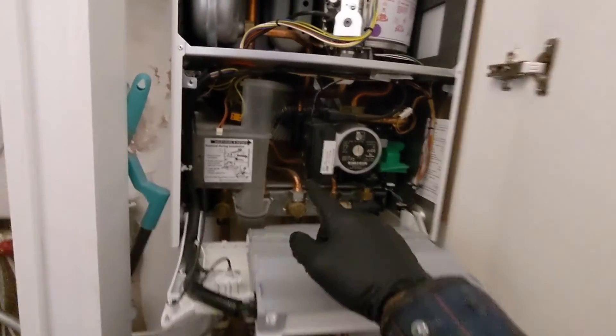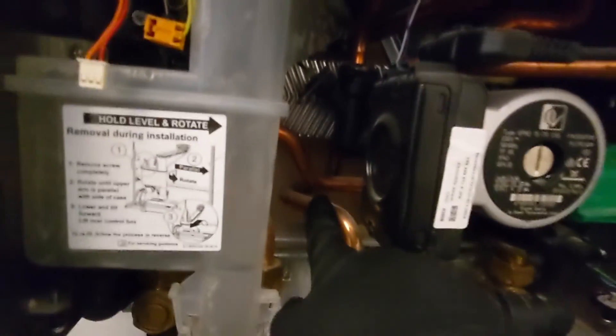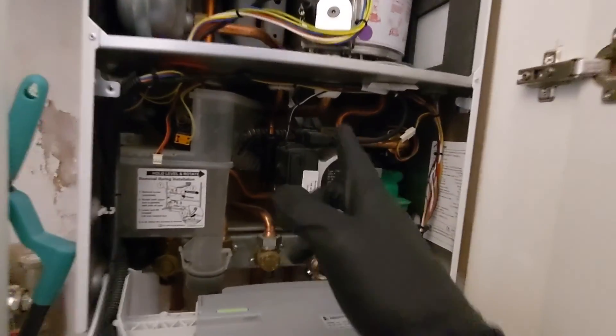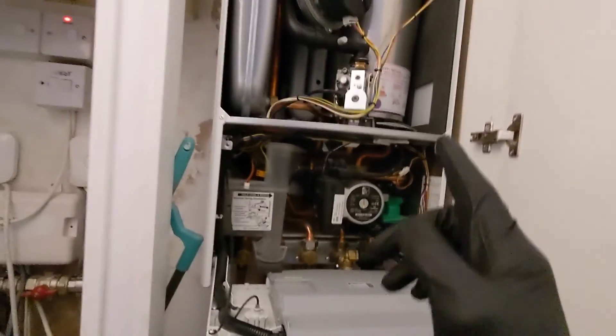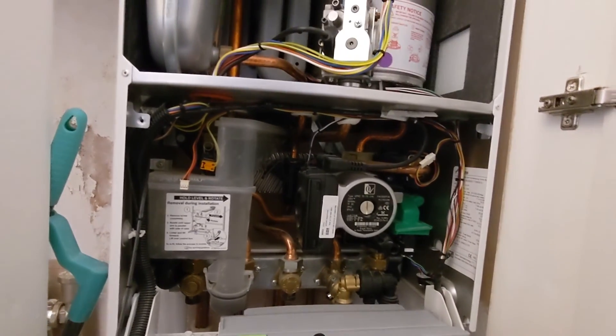These ones are not like the older styles where I could drop the plate out the back, because you've got the gas pipe here in the way. I've tried it before but that gets in the way, so it looks like I'll probably have to take the pump and everything out and then take the plate out the old way. I'll see if there's a way I can drop it out the back by looking underneath, but from my first attempt on the ERP ones I couldn't do it. I think I have seen a couple of people do it before, so I'll give it a try — if not, we'll just do it the long way by taking the pump out and go from there.